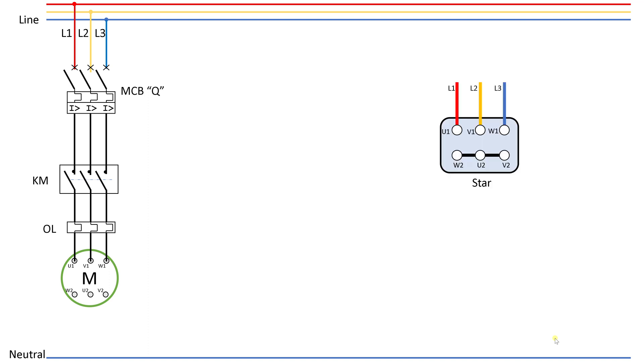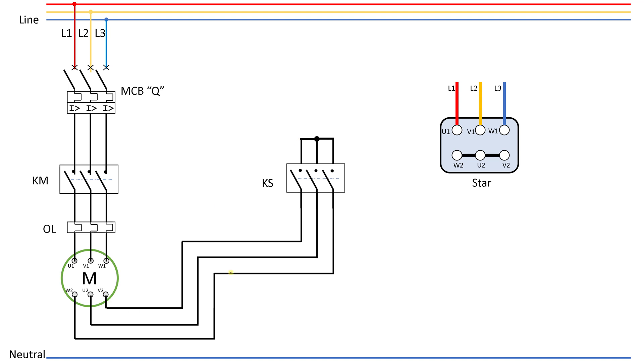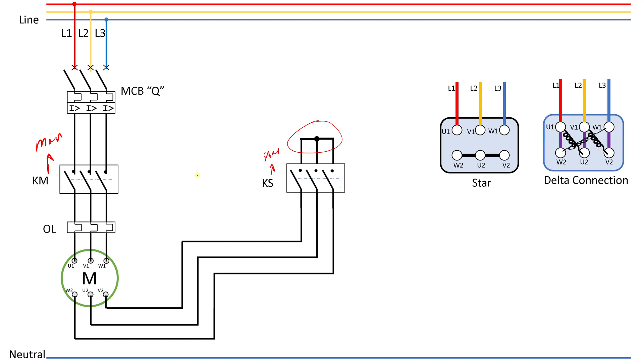To connect our motor in star, let's review the star connection. We need to shorten the terminals through a metal connector, and when we use a contactor we connect the motor wires through it so they are shortened. KM here means main contactor, and KS means star contactor. The main contactor will always be on, while the star contactor will be on for about 10 seconds, then turn off, and then the delta contactor takes over.